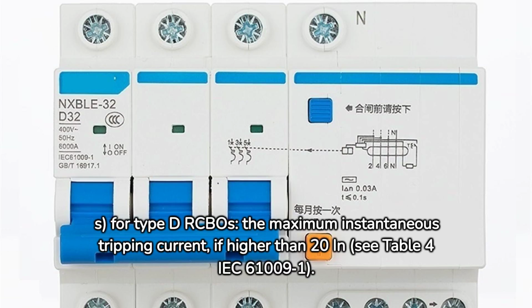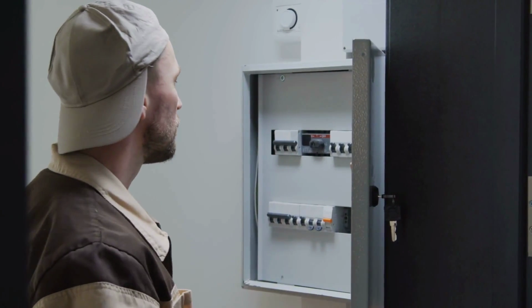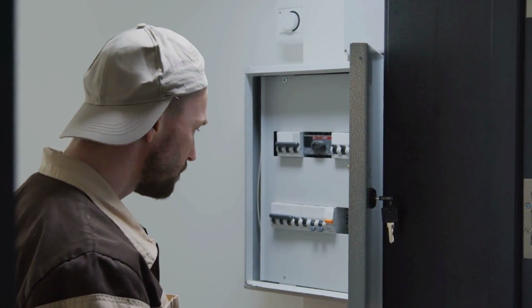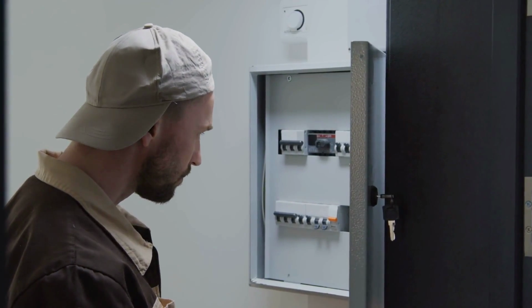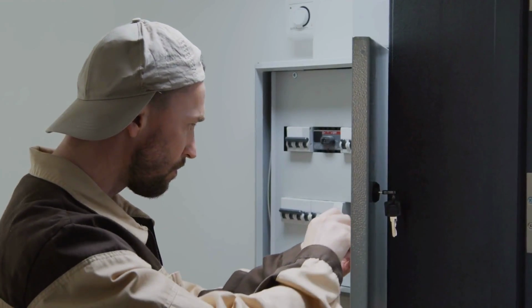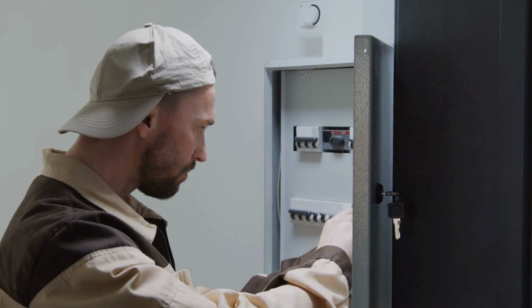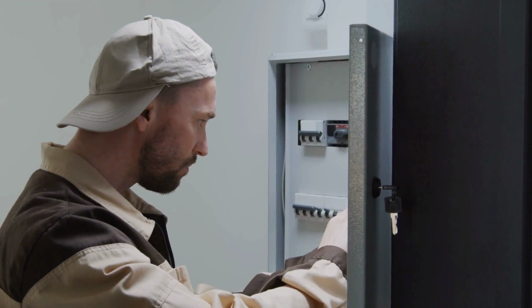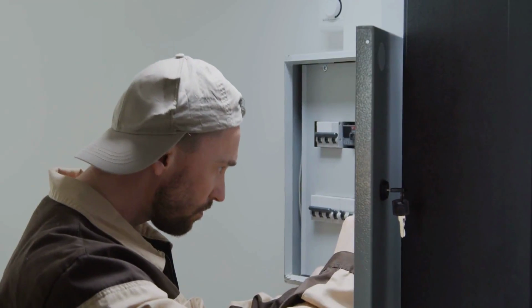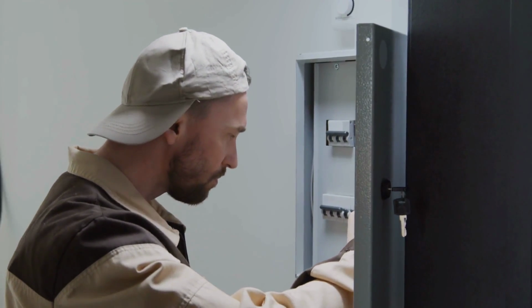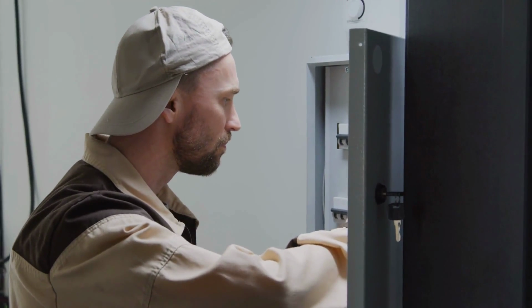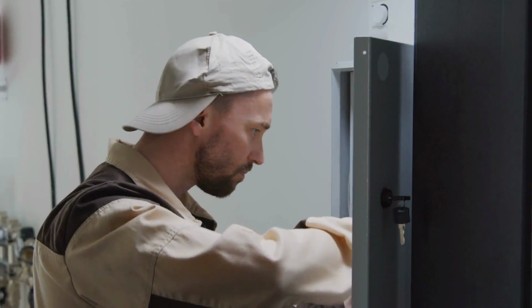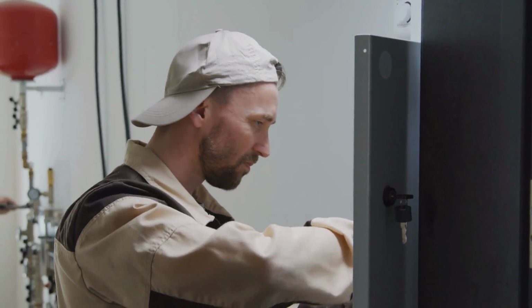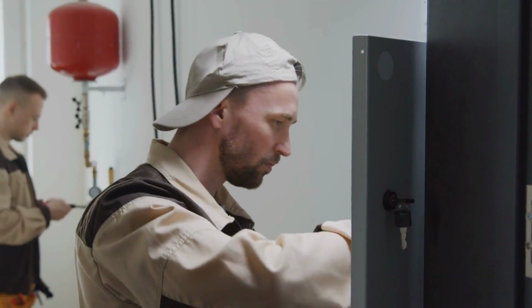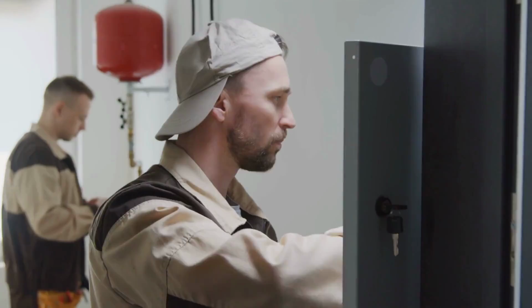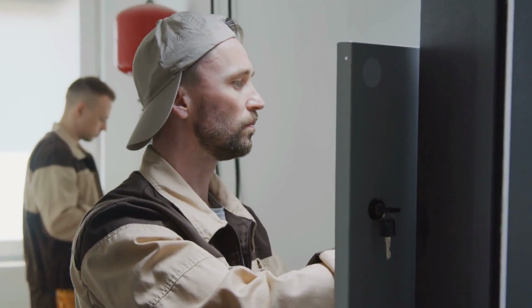If, for small devices, the space available does not allow all the above data to be marked, at least the information under D, F, N, P, and R, only for type A, shall be marked and visible when the device is installed. The information under A, B, C, H, L, R, only for type A, C, and S, may be marked on the side or on the back of the device and be visible only before the device is installed. The information under Q may be on the inside of any cover which has to be removed in order to connect the supply wires. Any remaining information not marked shall be given in the manufacturer's catalogs.